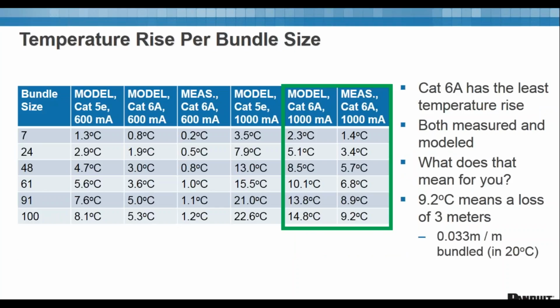I've been asked the question before: what if I have 24-cable bundles or 48-cable bundles through most of the installation, but then I have a firestop or some area where it's coming through a wall where I have to use really big bundles? Do I need to worry about the effect of that big bundle over the whole system, or is it just impacting that region? The answer is it's just impacting that region where it's occurring.